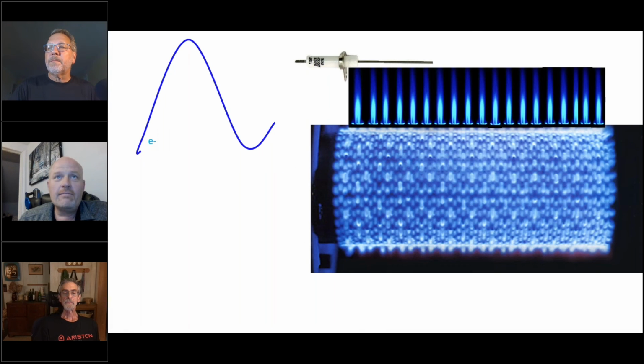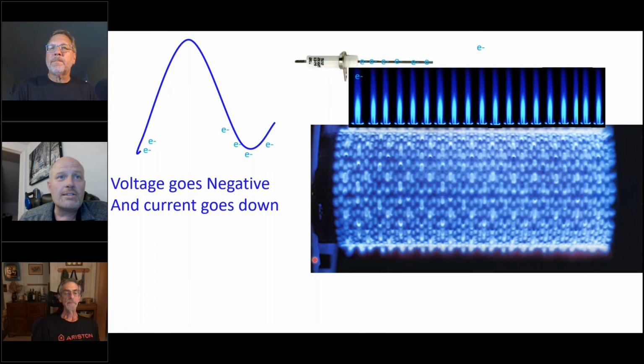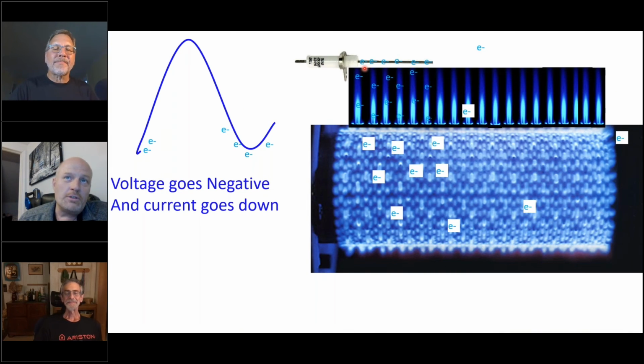And so here's my handiwork. I know Bob Ross has got nothing on me. As our voltage goes negative, for this example, the electrons will jump out of the flame rod and conduct through the flame. The flame is like a piece of wire, and they shoot out and stick to the burner. Basically, the electricity always wants to go to ground. So electrons come out, they go to ground.